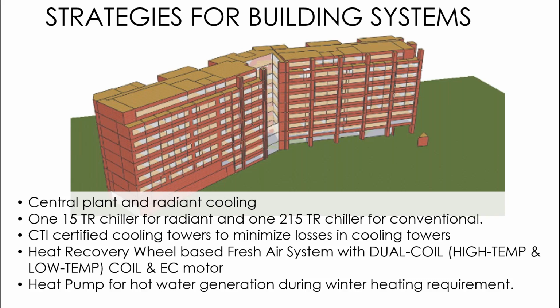That heat recovery is also with a dual coil. Dual coil means one is the cooling coil coming from a radiant chiller, and the other cooling coil is coming from the conventional chiller. We should also be mindful of the fact that a conventional chiller works at 7 degrees Celsius, 12 degrees Celsius, which means that it supplies chilled water to the air handling unit at 7 degrees Celsius and takes that hot water back at 12 degrees Celsius, whereas a radiant chiller works at 15 to 19 degrees. It supplies at 15 degrees and takes back at 19.